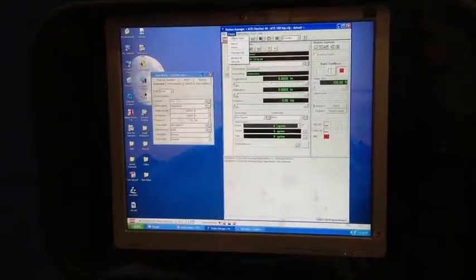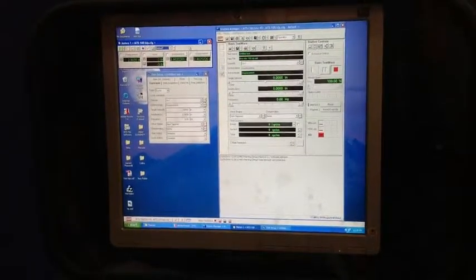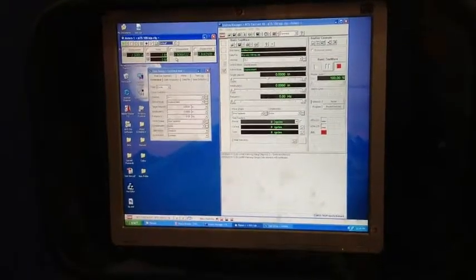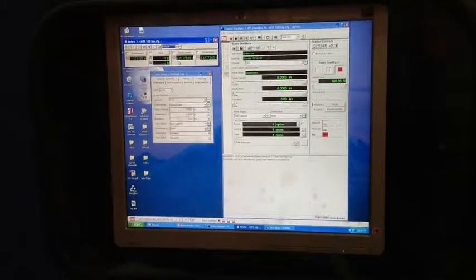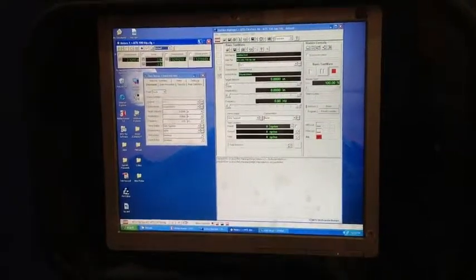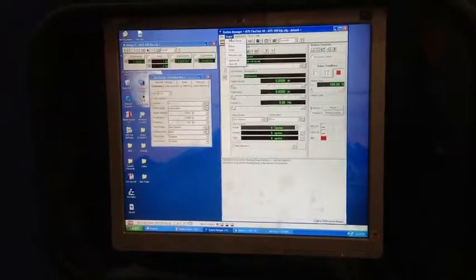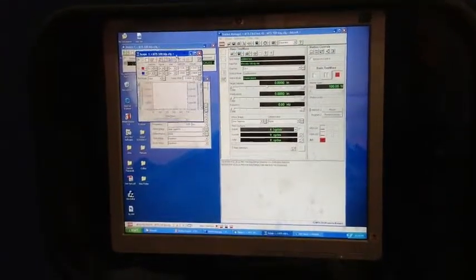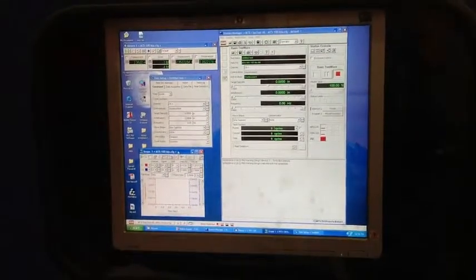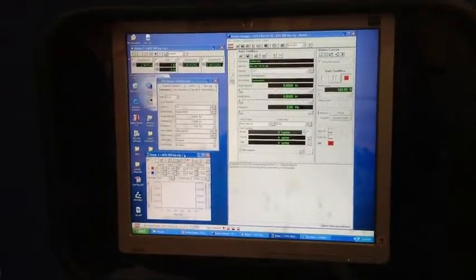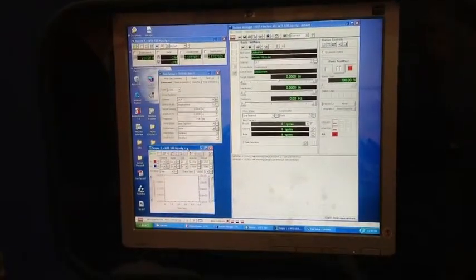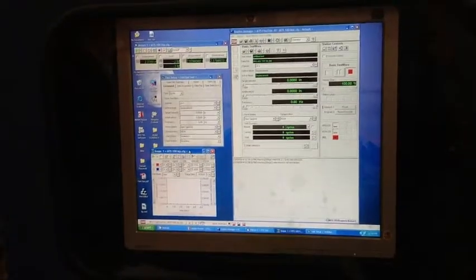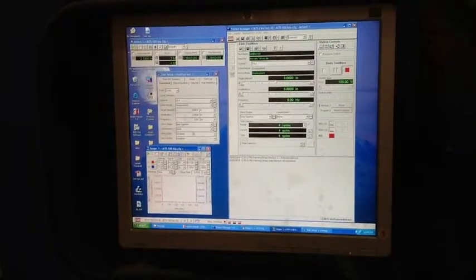So you go to display, then meters. Then you can see this window. This will allow you to check the force versus displacement at any time. And the second one is also under display scope. This is a plot of displacement versus time. And you can check your displacement versus time plot at any time to make sure that your test is running or not.